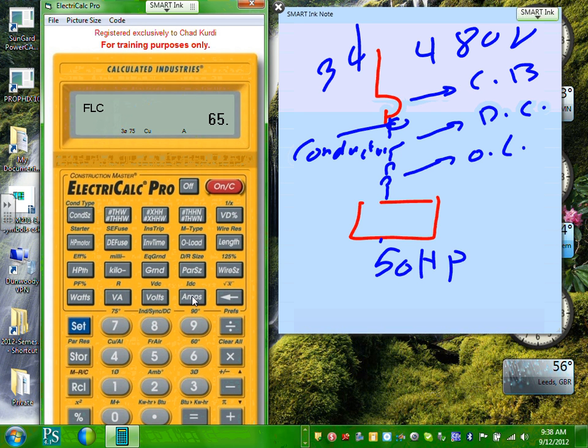Can I have thumbs up, Chad? 65. Okay, now, since it's a motor, when we size the conductor, guys, just hit it. You don't have to type anything. When you size a conductor for motors, it's a continuous load. So hit set and wire size. Here's the 4 copper that you're going to use for this conductor. Set copper wire size. Can I have thumbs up, Chad? Here's a conductor. How many conductors? 3. Why 3? Three-phase. And the size is 4 copper.